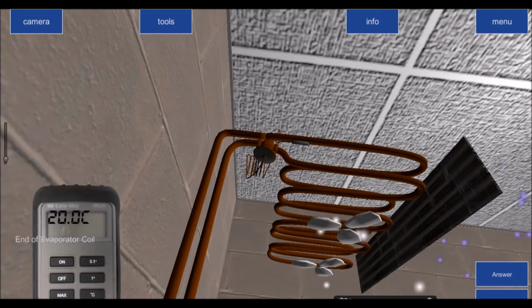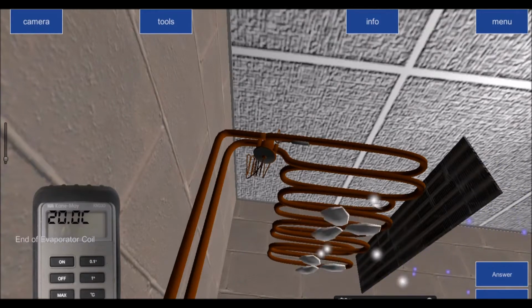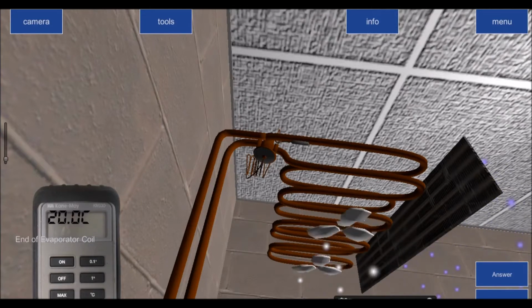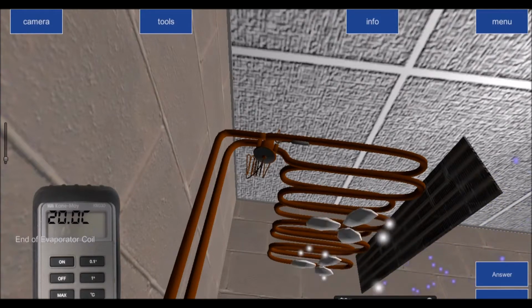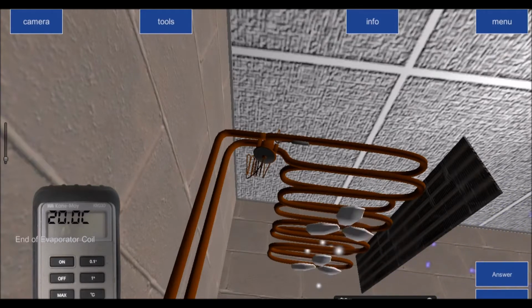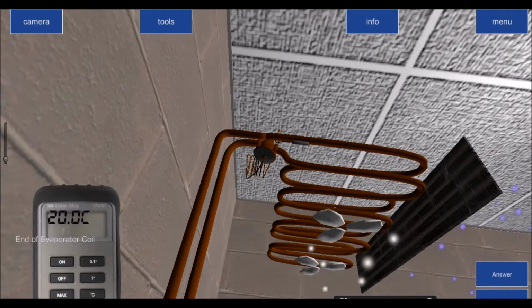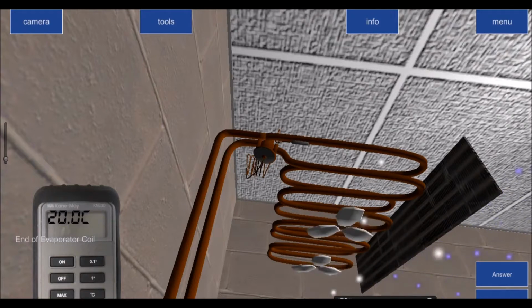But the other reason for superheat, or the only other reason why we have superheat in the evaporator, is to make sure that the compressor only has vapor coming back to it. Our refrigeration compressors only pump vapor. They do not pump liquid. So superheat has been built in, or engineered in, to the process so that it can protect the compressor from liquid slugs getting back. So that's the only reason why superheat takes place inside the evaporator.